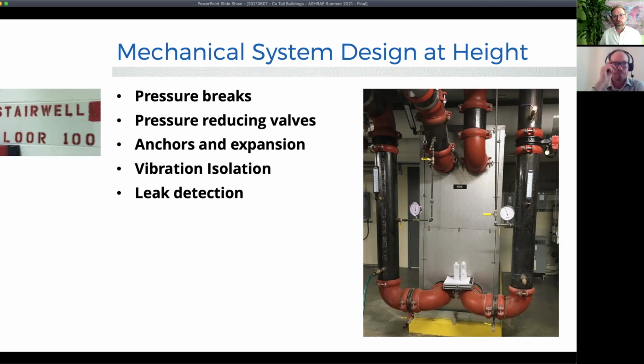Somebody can get a chiller, for instance, where the condenser bundle isn't sized for the correct pressure rating, and it just gets missed. So you want to make sure you're looking at these things as a second set of eyes. When it comes to the commissioning of these systems, pressure reducing valves are common in the plumbing systems for domestic hot water, domestic cold water, things of that nature.